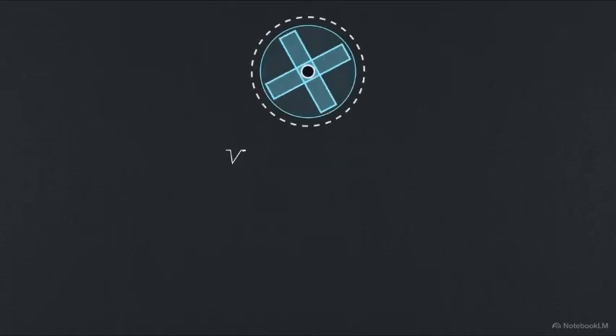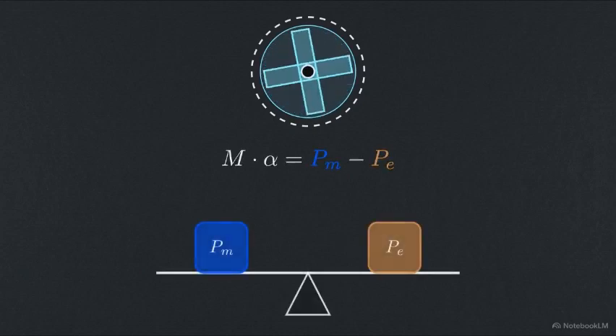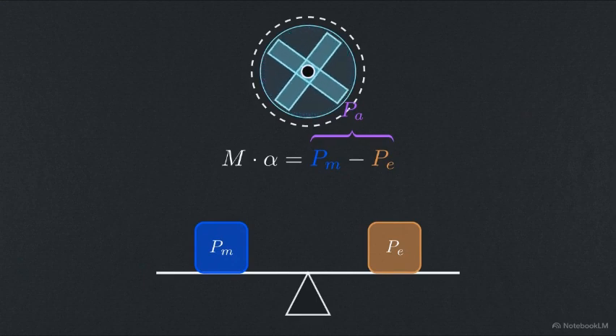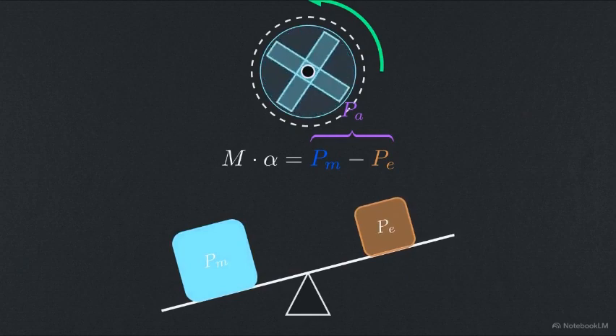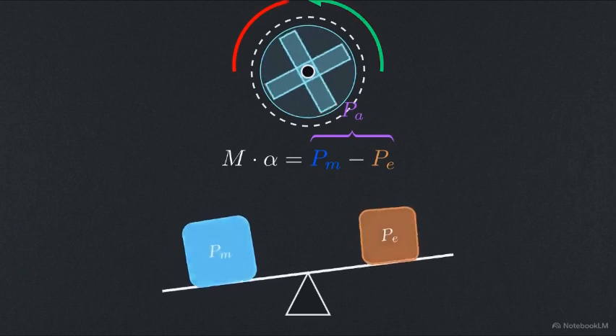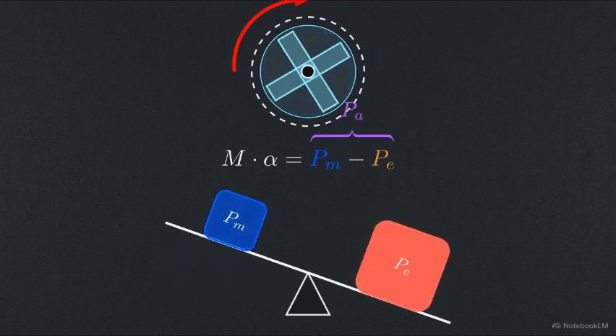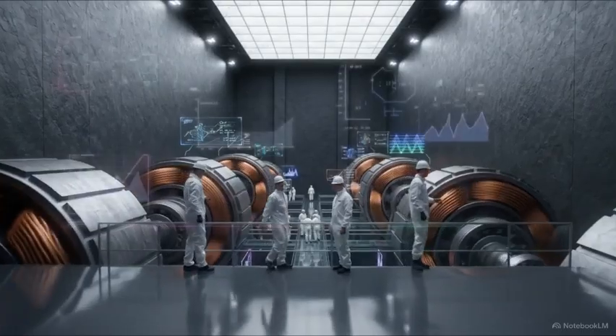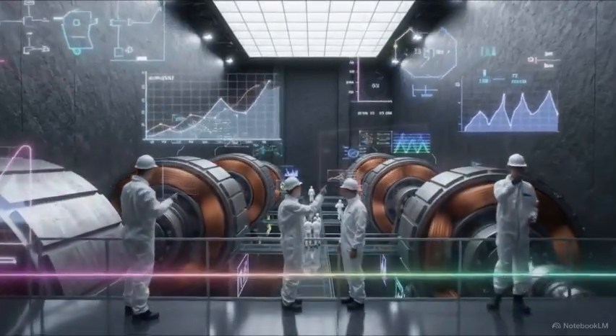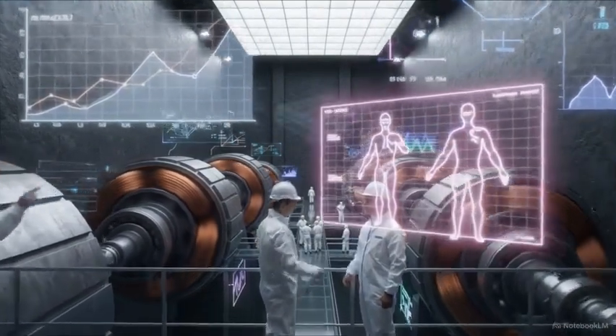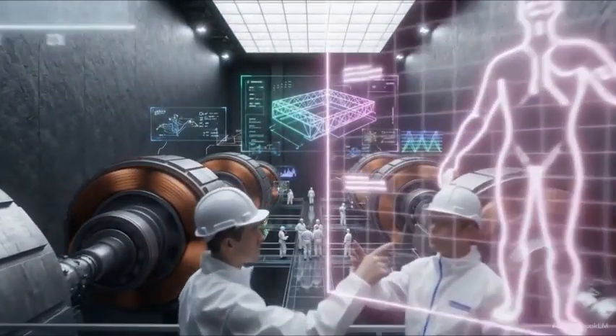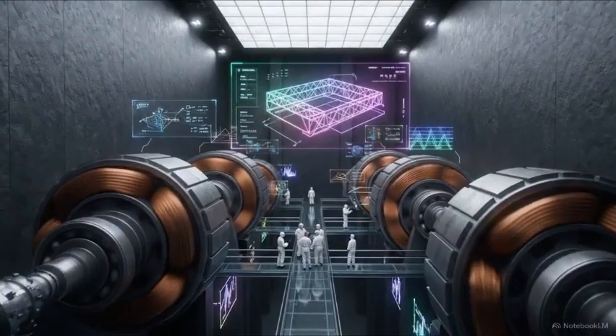This diagram visualizes the swing equation as a dynamic scale, balancing mechanical power input, PM, against electrical power output, PE. Their difference is accelerating power, PA. When PA is positive, meaning input exceeds demand, the rotor physically accelerates. If negative, the machine violently decelerates. A power swing is a literal physical rotation. Colossal machines weighing hundreds of tons fight against the physics of momentum to maintain systemic balance.